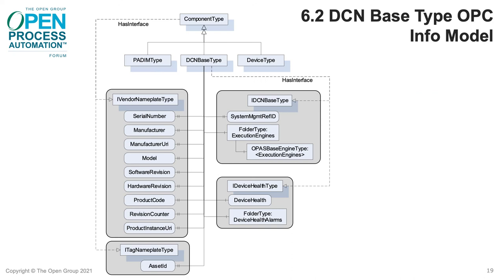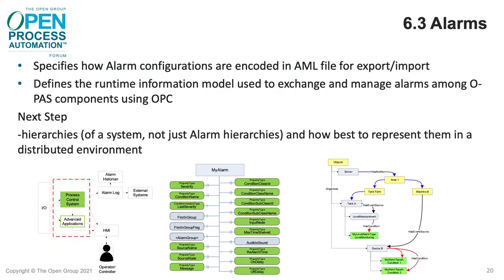Here's an OPC information model of a DCN providing the same interfaces as PA-DIM for vendor information such as make, model, and serial number, health information, and we've added a function block engine. Part 6.3 specifies how alarm configurations are encoded in AML for export and import, and it defines the runtime information model used to exchange and manage alarms among OPAS components using OPC. Next, we'll be defining hierarchies and how best to represent them in a distributed environment.